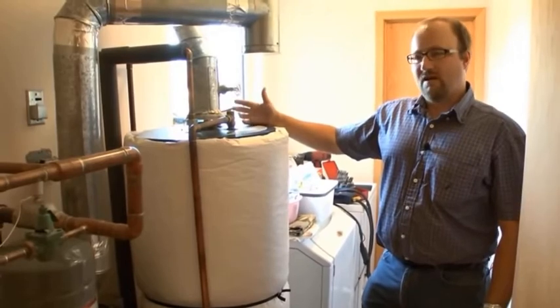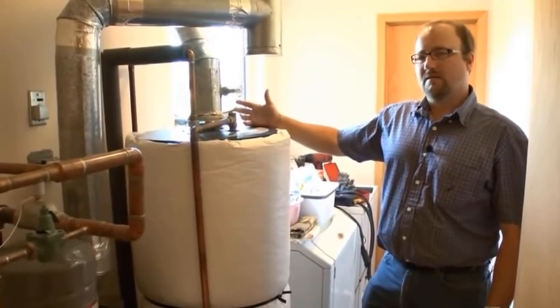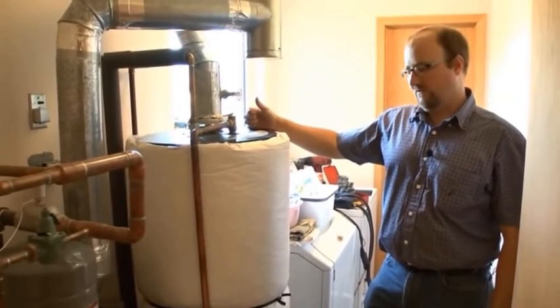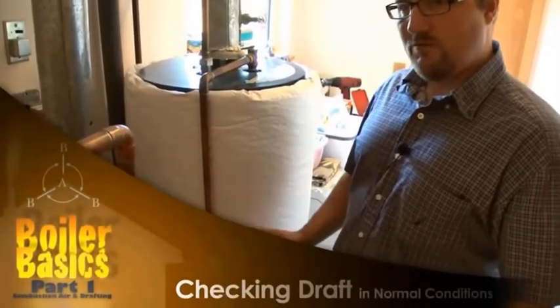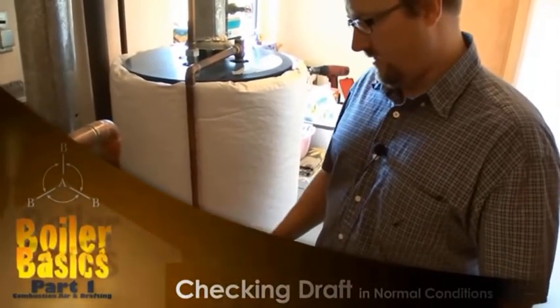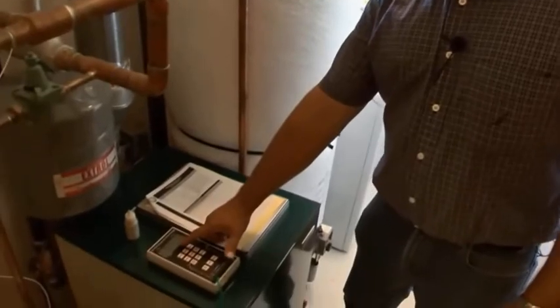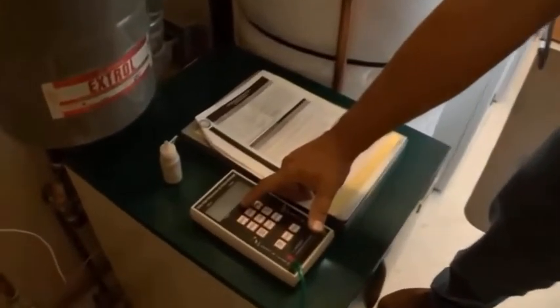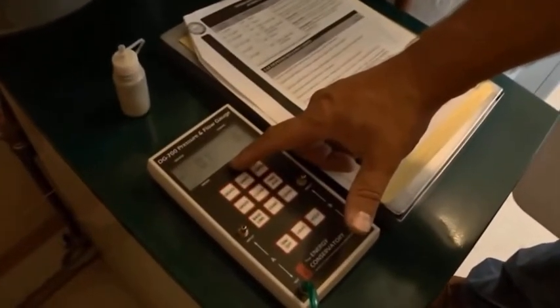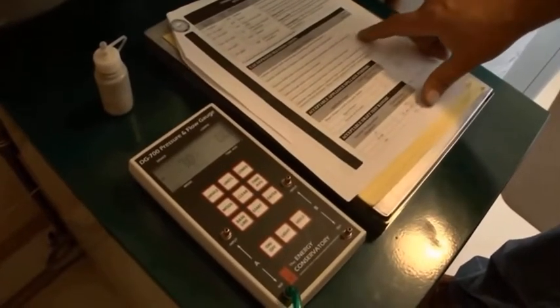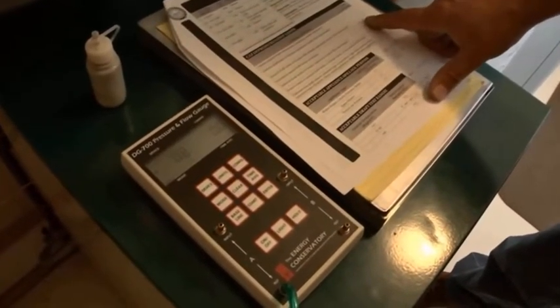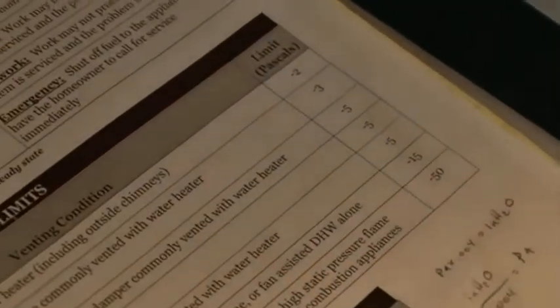We would have to solve the problem before we could continue with further work. At this point, we have all the doors open, the fans are off, and you can see our baseline pressure reading is definitely below the threshold. We're okay at this point, so we can continue.